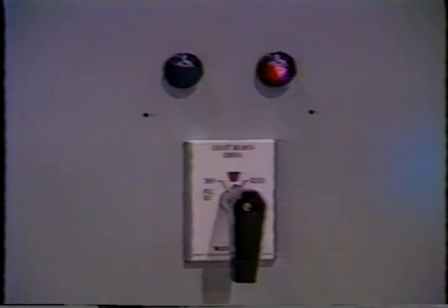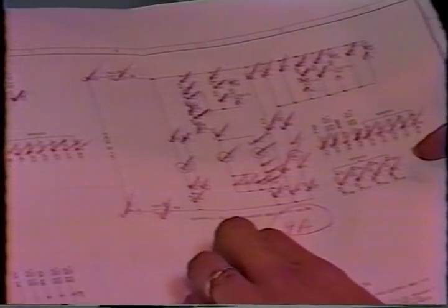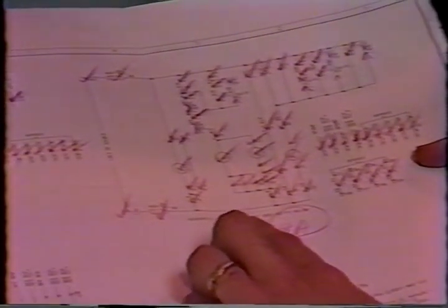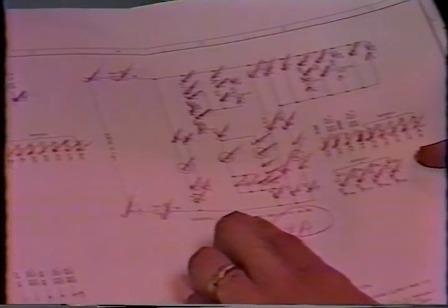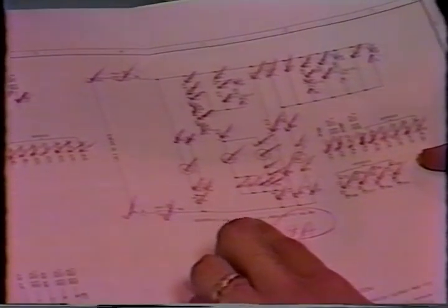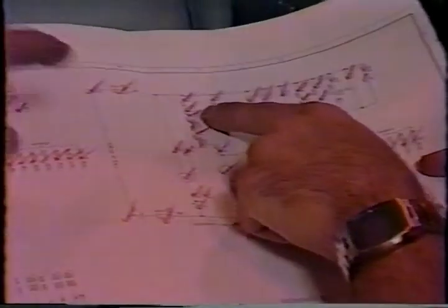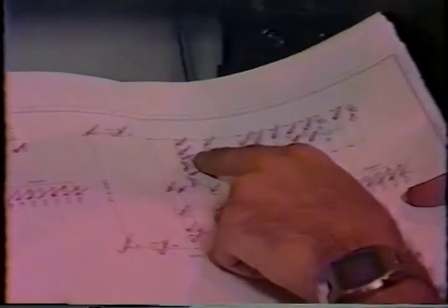In a DC control scheme, the red light supervises the trip coil and indicates the trip coil circuit has continuity. These diagrams comply with the requirements set forth by IEEE, NEMA, and ANSI. All of the schemes are designed to coordinate electrically with the mechanical design of the breaker.